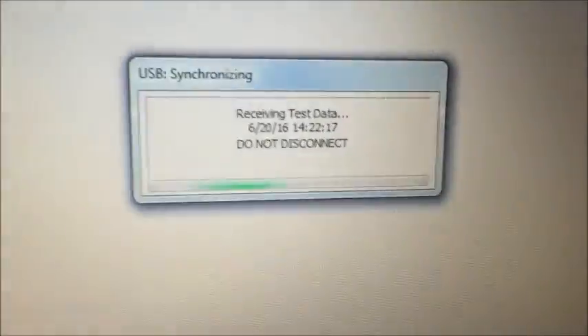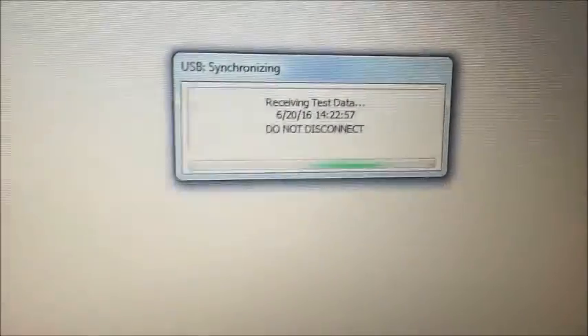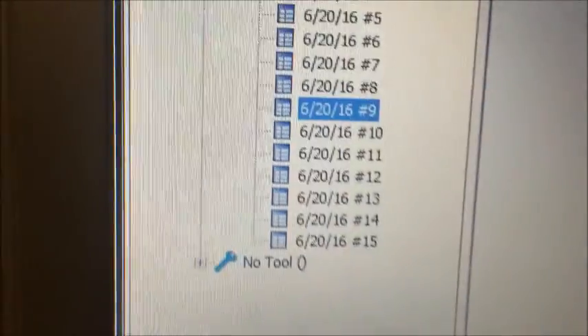So the other way to collect the data from this unit is a USB cable that's supplied with it. It's plugged straight into the back of the unit. You can set the software to do an automatic sync, so as soon as I plug in, the software should start recognizing the tool. The tester will start recognizing, then the software starts downloading any new data. So we should see test number 10, 11, 12, 15 come up.